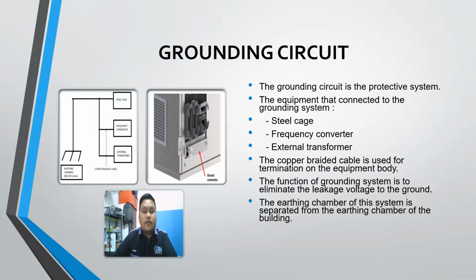From the block diagram above, the grounding is connected from the earthing chamber to the steel cage, frequency converter, and external transformer. The connection of the earthing uses copper braided cable that terminates to the equipment body. This connection is to prevent equipment that has a conductive body from leakage voltage and prevent harming the student or other equipment. The earthing chamber for the lab is separated from the earthing chamber of the building. This is to ensure that there is no disturbance from surrounding machines entering the test field. In case of failure, the earth potential of the surrounding does not rise and cause damage to electrical equipment.